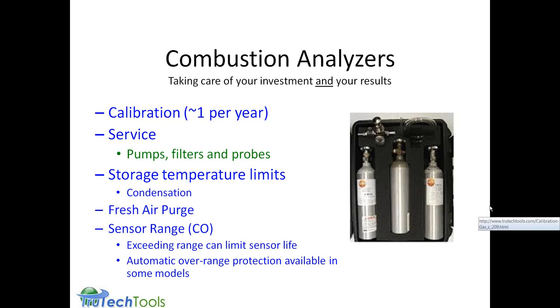Got a question here. Can the 327 or 330 be used as a gas leak sensor for the gases tested? Neither of the meters has a built-in combustible gas sensor, if that's what you mean by gas leak sensor. Combustible gases are like propane, methane, natural gas. The 330 has an optional probe that can be plugged into it to be used as a gas leak sensor. But frankly, that probe is way above the cost of an equivalent standalone type meter. Unless you're really motivated to get one, I wouldn't recommend it; it's better to get a separate device rather than a connectable probe. I think the probe is about $330, where you can get a standalone gas leak detector for about $195. That's a very good quality and uses the same kind of technology.